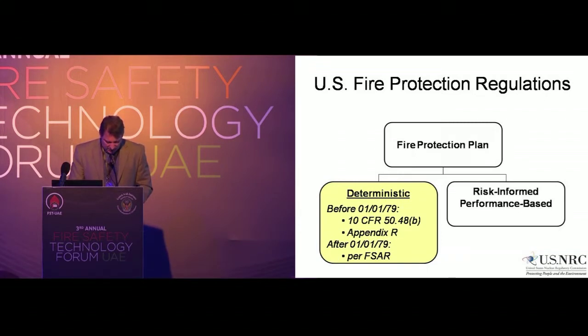In some cases, the requirements set forth weren't practical for every plant or existing plants, or there was a more favorable approach to achieve an equivalent level of safety. So as a matter of fact, because many of these plants were already constructed, they couldn't, for example, all meet the 20-foot separation between trains requirement. So they had to apply for exemptions and in essence show an equivalent or a higher level of safety was accomplished through another means. This led to a multitude of exemptions and really complicated the fire protection licensing basis.